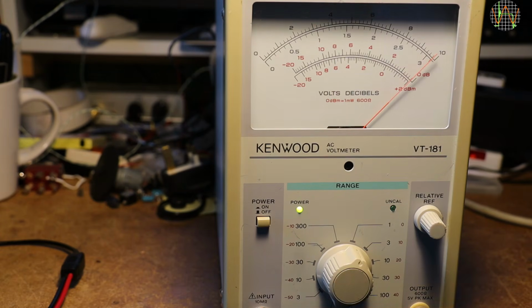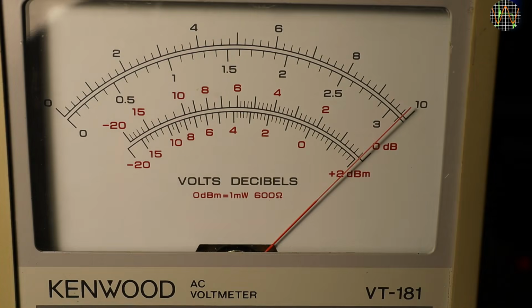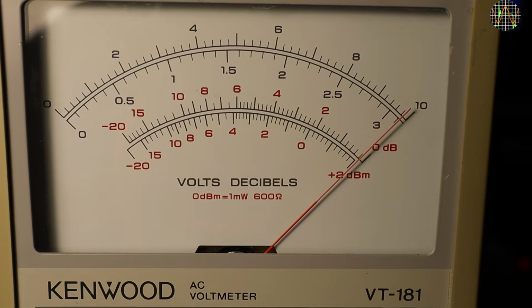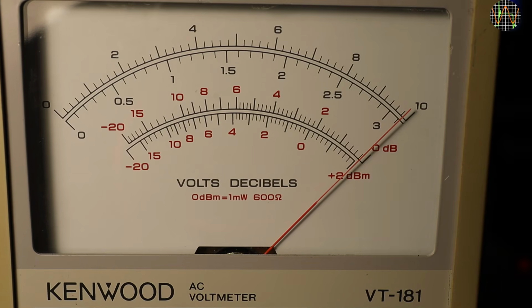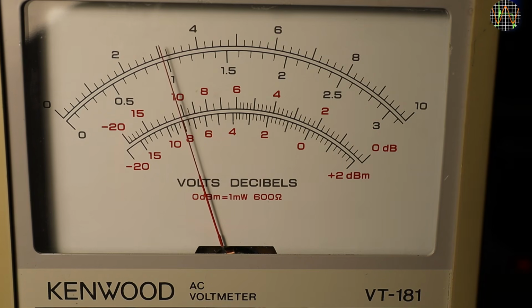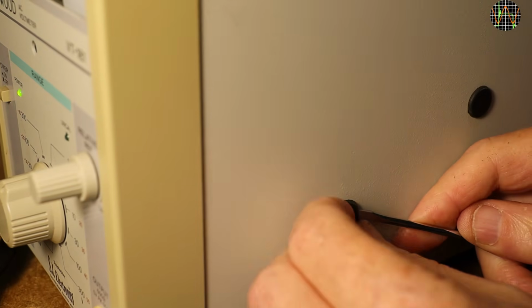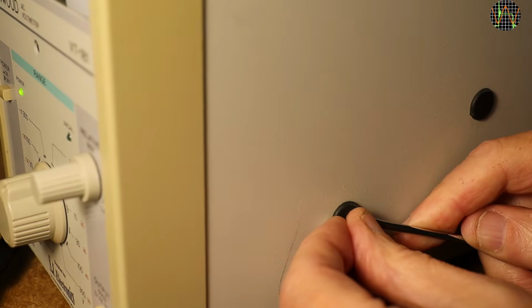Turning to the 1 volt range, and we have nearly full scale with the needle close to the 10. A closer view of the 1 volt in the 1 volt range. It's sadly not a mirror scale, as for example in my TM3B I showed and calibrated in an earlier video. In the 3 volt range, the needle should be at 1 and is slightly below. There are 3 calibration points. They are accessible from the outside once the 3 rubber plugs and the housing are removed.